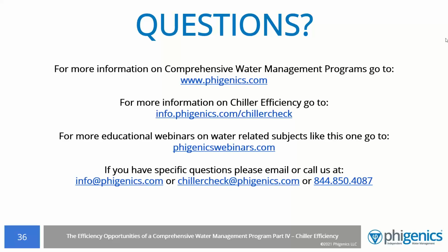Light load surge occurs under very light load conditions, and I'm not really sure, with the new chillers today, what process you would take. I haven't heard much of that lately, to be honest with you. So I don't really have a good recommendation on the light load side, other than to talk to the manufacturer, say, these are the conditions my chiller is running at, give them a full set of log readings, and say, tell me why my chiller is surging under these conditions, and what should I do to correct it.